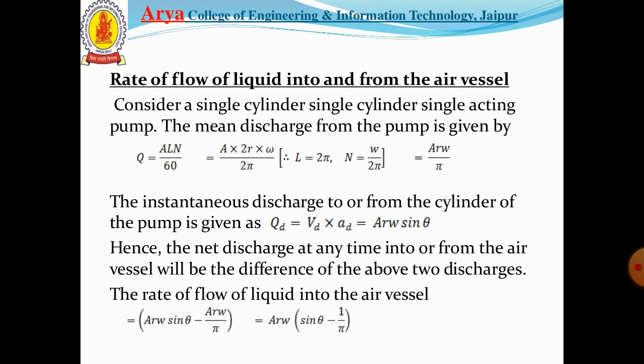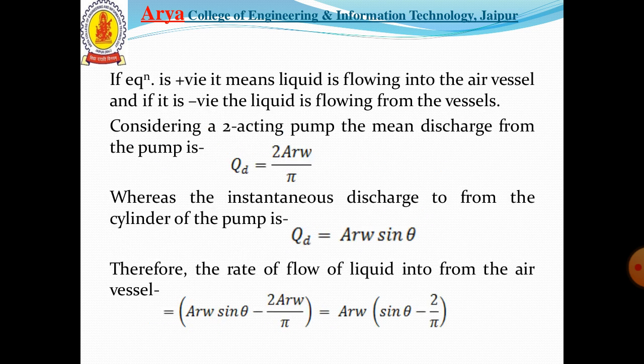If the equation yields a positive value, it means the liquid is flowing into the air vessel; if it yields a negative value, the liquid is flowing out of the vessel. Considering a double acting pump, the mean discharge from the pump is 2A·r·ω/π.